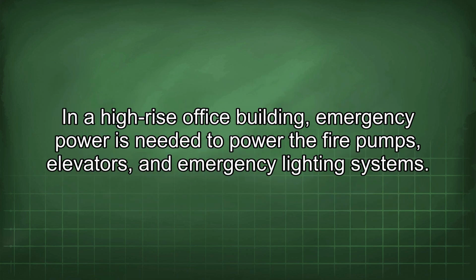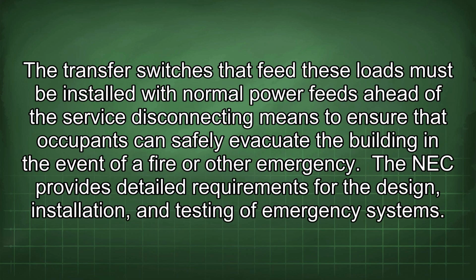In a high-rise office building, emergency power is needed to power the fire pumps, elevators, and emergency lighting systems. The transfer switches that feed these loads must be installed with normal power feeds ahead of the service disconnecting means to ensure that occupants can safely evacuate the building in the event of a fire or other emergency.